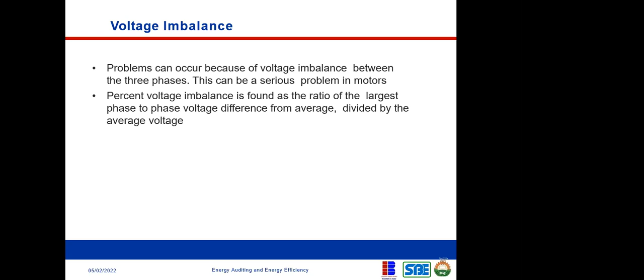Problems can occur because of voltage imbalance between three-phase systems. Now, this can be a serious problem in motors. Remember, most motors, especially industrial motors, use three phases. So when there's voltage imbalance, it creates problems in the systems. The percentage voltage imbalance is found as the ratio of the largest phase-to-phase voltage difference from the average, divided by the average voltage. Don't worry, we're going to illustrate this. That sounds like a long sentence.